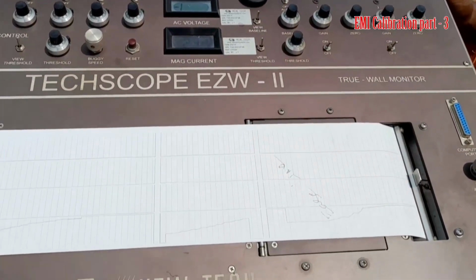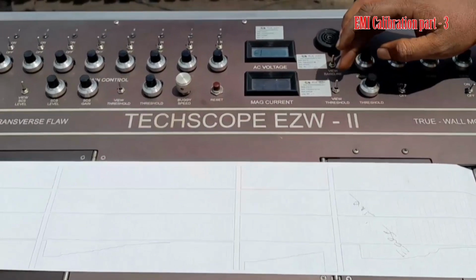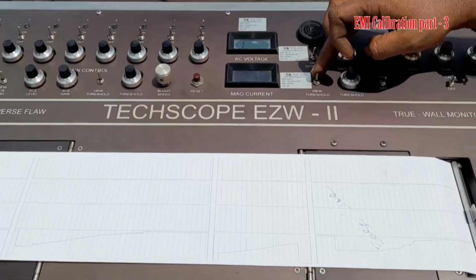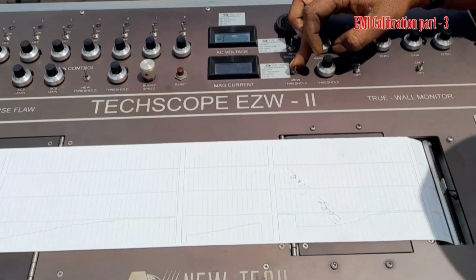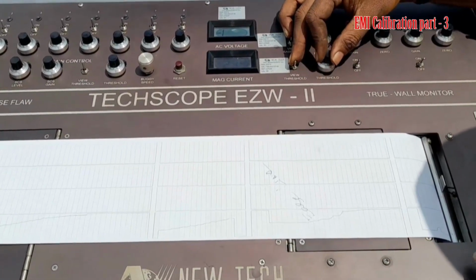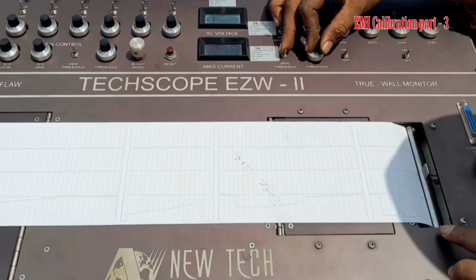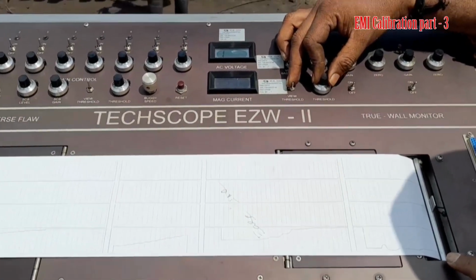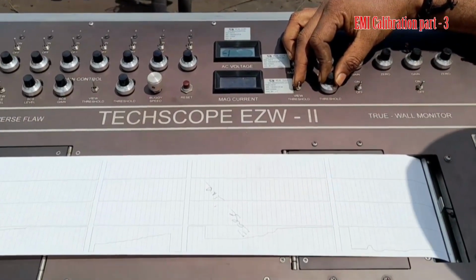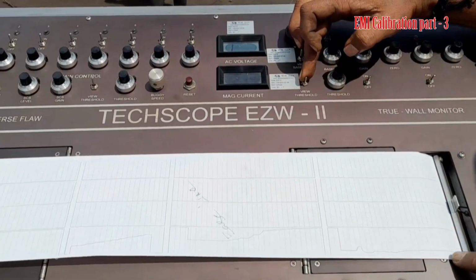Second is threshold. Switch on the mag, switch on the printer, then hold the threshold line toggle switch and adjust the value to 10 mm or 15 mm or 5 mm below the wall monitoring layer. 10 mm is better. I also set up the machine at 10 mm. Your threshold is 10 mm. The same, these are the basic setup. There are 3 methods to calibrate the wall monitoring setup.